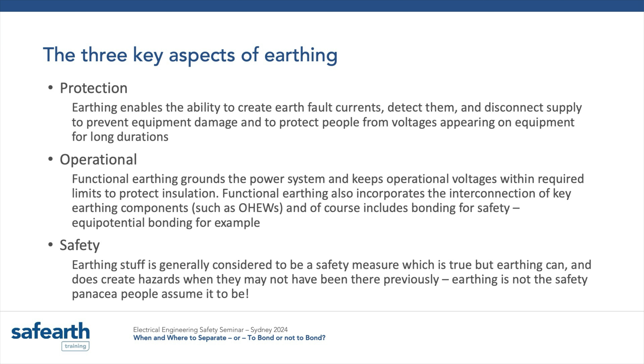I haven't spoken to this forum for a number of years, but I remember speaking when it was at Piedmont a few years ago, and I made that statement, and a lot of people looked at me like I'm an idiot. But one fella, Bob Lee, God love him, his son works with us now at Safearth as an instruments engineer, but Bob Lee got up and said, absolutely, that's exactly what I want to do at my pit. But you've got to be careful, it probably creates other flow-on effects you weren't considering. You get a trip down in your mine and all the power goes out, so you've got to have some system in place to manage that. But like I say, if earthing was all about safety, we'd be tripping things way quicker than we do.